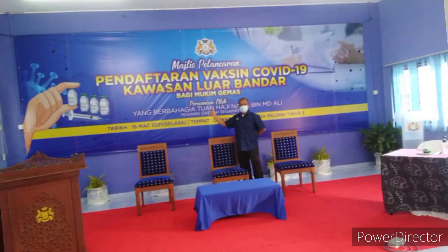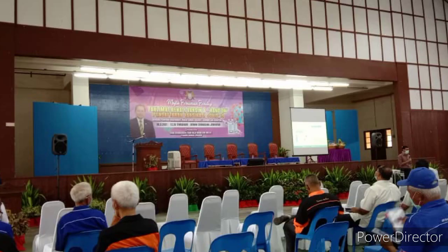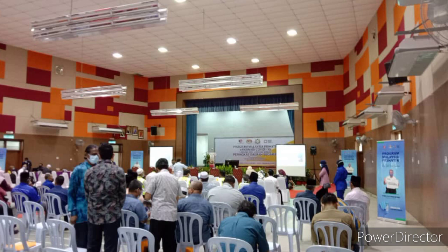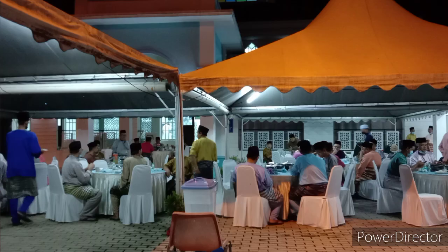The issue I wanted to solve is the tripping problem, which interrupts official ceremonies. The added temporary electrical installation increases the load close to the maximum capability of the incoming cable. Overcurrent occurs without an earlier warning system, and it is difficult to monitor the current value at the incoming cable due to the height or compact placement of the meter kiosk or incoming cable.